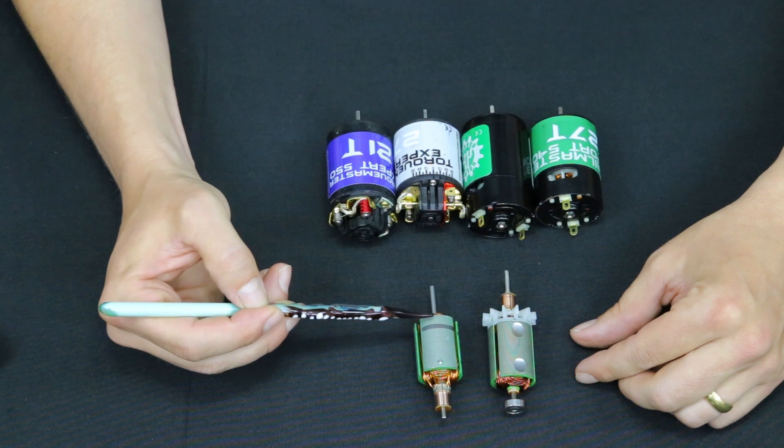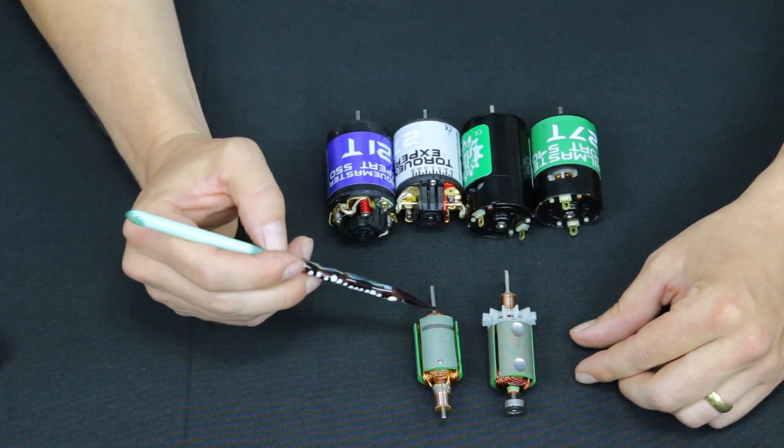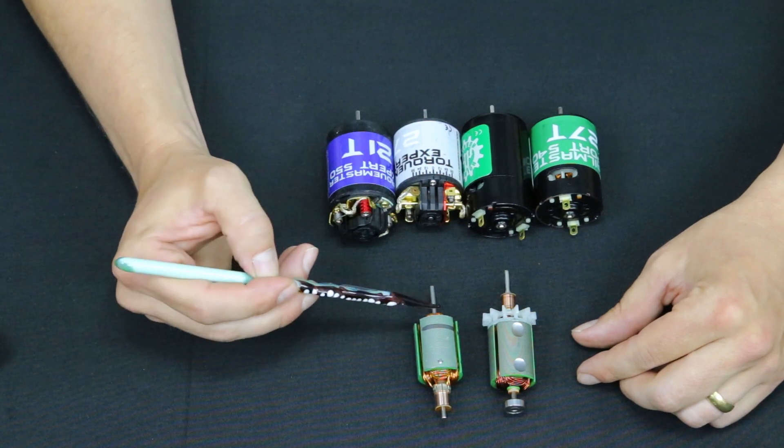the laminations will have a little bit of losses inside, and that's generally called steel losses or eddy currents from within the lamination itself.